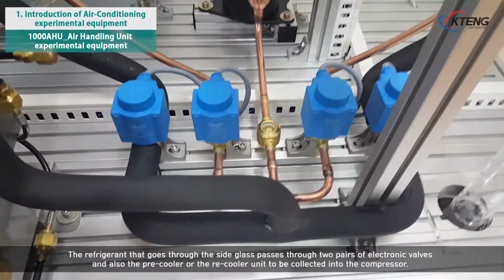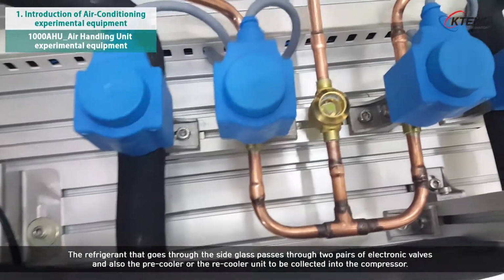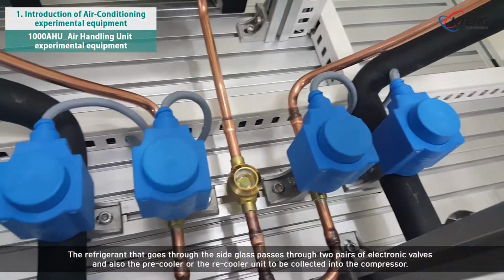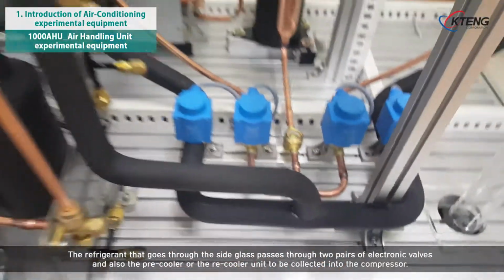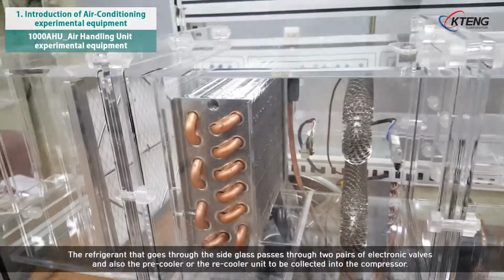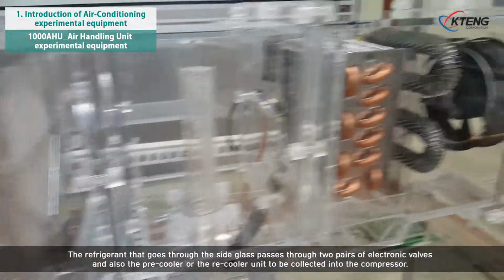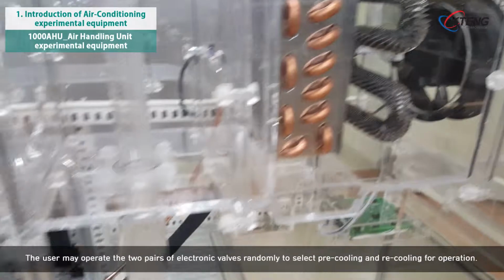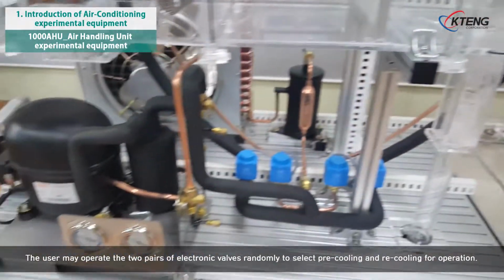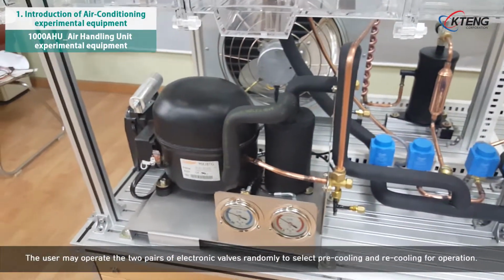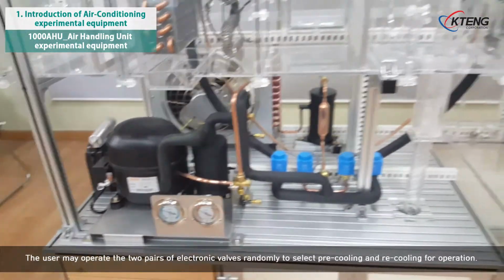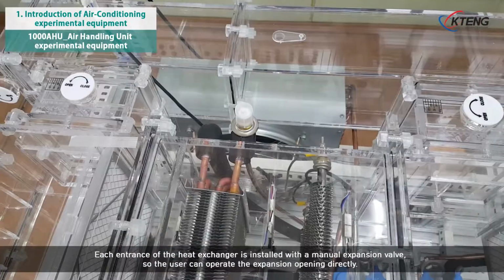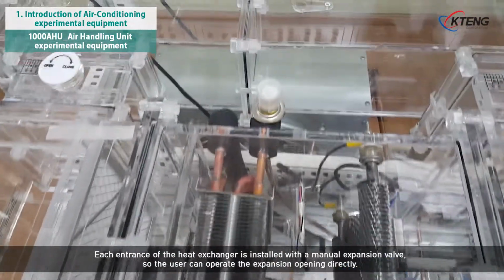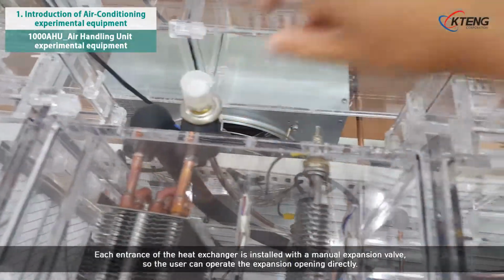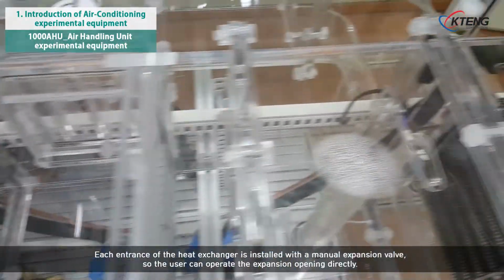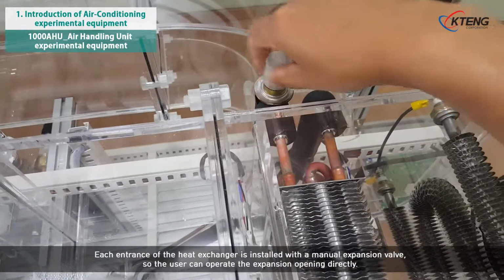The refrigerant that goes through the side glass passes through 2 pairs of electronic valves and also the pre-cooler or the recooler unit to be collected into the compressor. The user may operate the 2 pairs of electronic valves randomly to select pre-cooling and recooling for operation. Each entrance of the heat exchanger is installed with a manual expansion valve, so the user can operate the expansion opening directly.